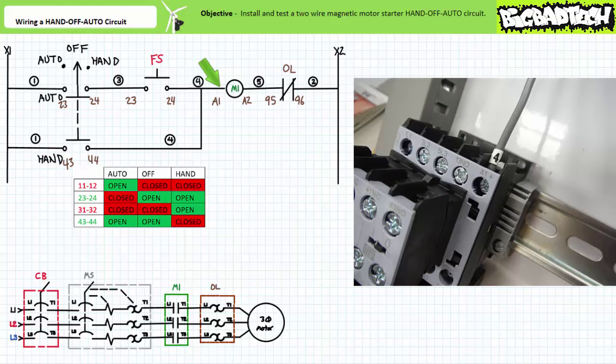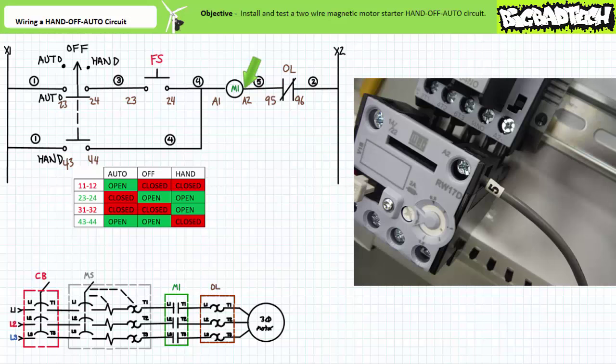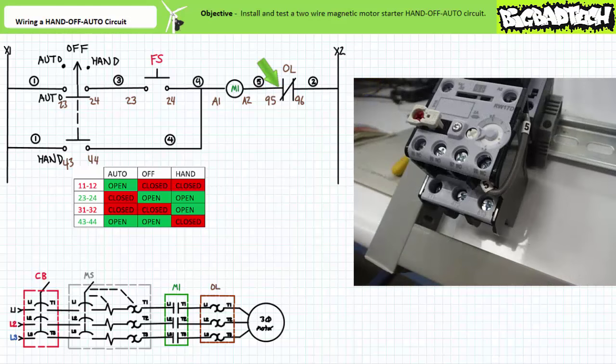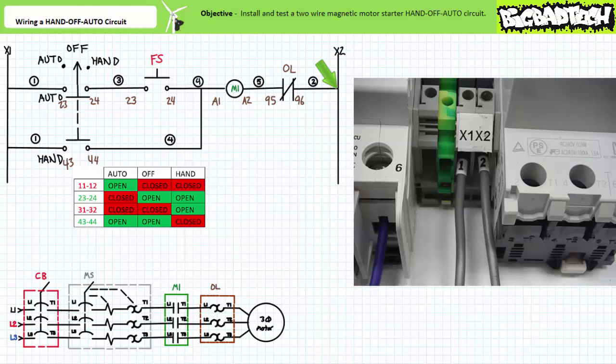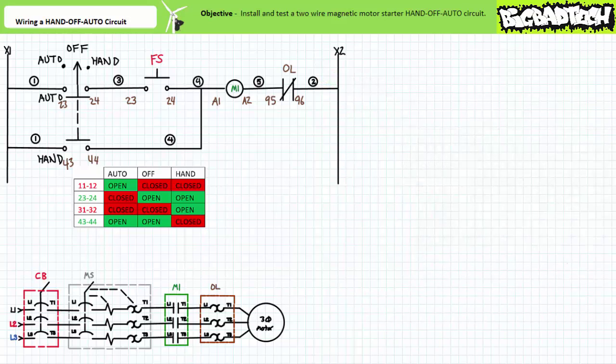Here's where you get to appreciate the cunningness of this particular manufacturer. Wire five comes out of the still-accessible A2 terminal of the contactor coil and goes right into the conveniently available 95 terminal of the normally closed overload contact — too easy. Wire two comes out of the 96 terminal of the normally closed overload contact and goes back to the grounded X2 side of the control transformer — I'm using the terminal block to make my life easy. Rung one is done; we can now move on to rung two.